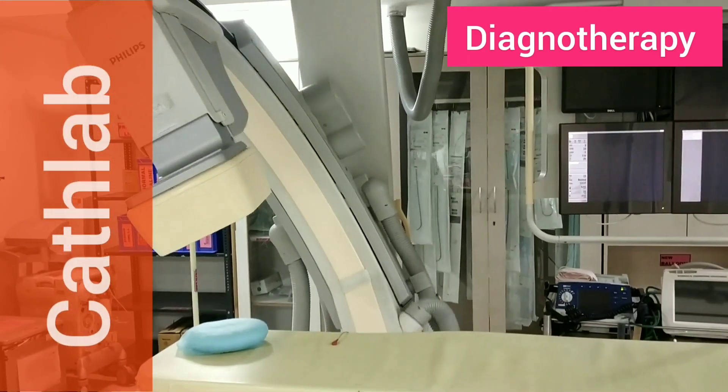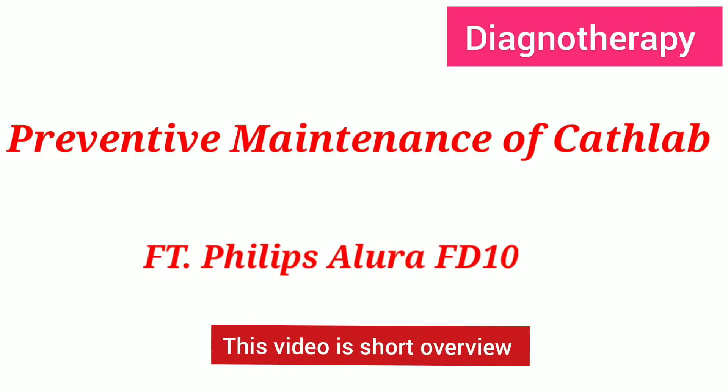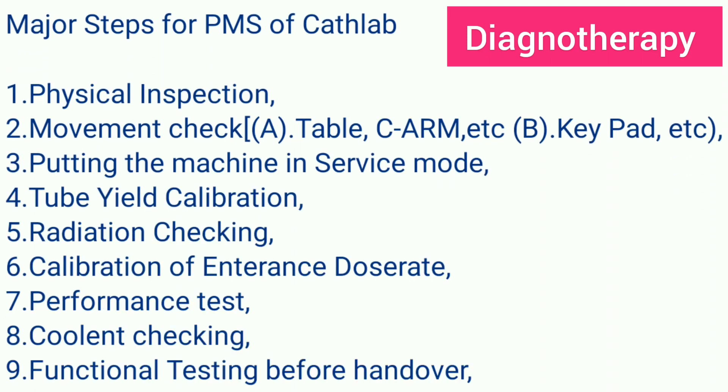In this video we will be seeing the preventive maintenance of a cath lab featuring the Philips Allura FD10. The major steps of PM of cath lab are: first, physical inspection; second, movement check of the table, C-ARM, keypads, and control movements — checking whether the keypad movements are giving correct movements or not.